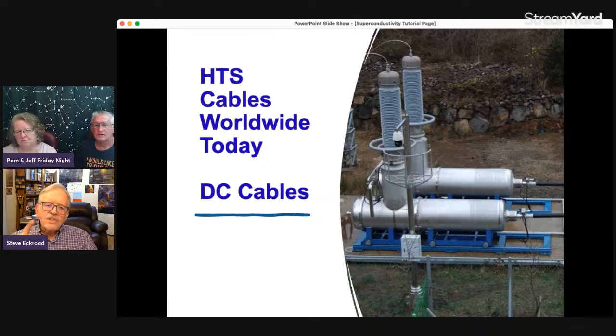But the alternating current causes an alternating magnetic field in the cable, and you get some losses. Anytime you're moving charges around, by Newton's second law, force equals mass times acceleration, you're moving particles, so you're going to expend energy. There are some losses, but very, very tiny. A DC superconductor really, genuinely, literally has zero losses, and that's one reason DC cables are attractive. Another reason is this: an AC cable, whether superconducting or not, is essentially a giant capacitor.